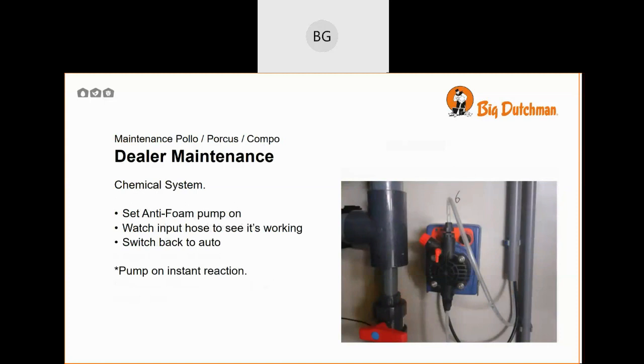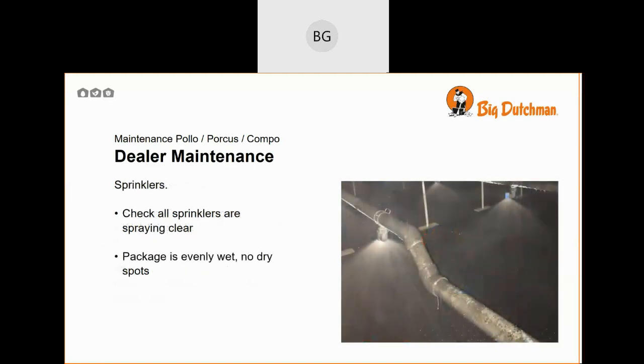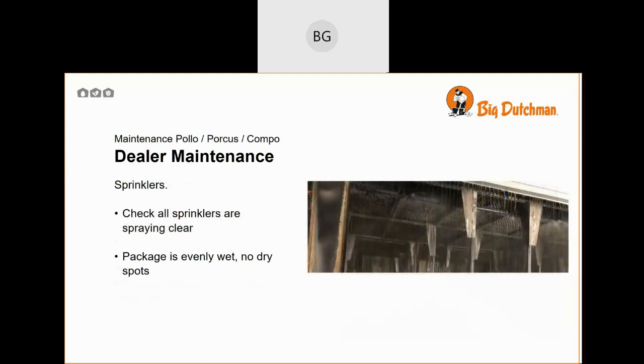For the anti-foam pump, set the anti-foam pump on and watch the input hose to see that it is actually pumping the anti-foam fluid in. Set the pump back to automatic. This pump should react instantaneously. Sprinklers: check that all of the sprinklers spray clearly and that the package is evenly wet with no dry spots. You should check the package both from above and below.